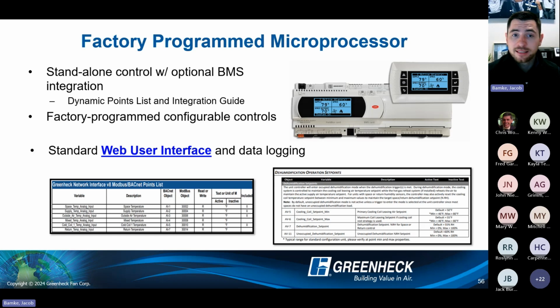Controls. So we have a standalone controls option with building management system integration. And a couple of things here. One is our controller is just a skeleton that we get from Carel. So based on all the different applications that we talked about, this controller can be configured based on how it's ordered for that application. It's factory programmed. And then if you have a building management system, the submittal comes with a dynamic points list. So based on selections, what points would you have the ability to read? What points would you have the ability to communicate to? And then we also have an integration guide, on the bottom right, that goes more in depth on how you use each point. What are the minimums and the maximums? What does it default to, so that you can easily configure that in the field as well.